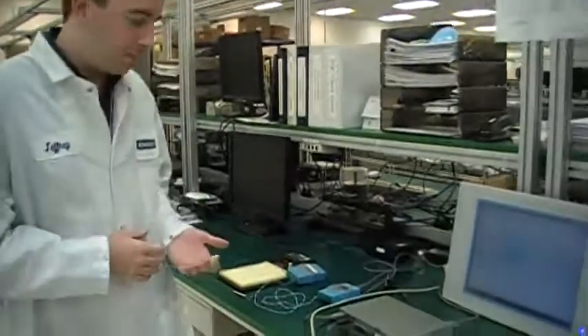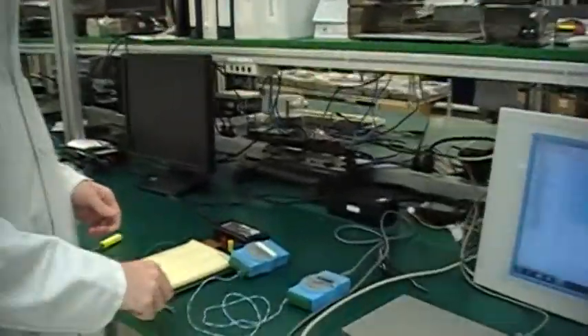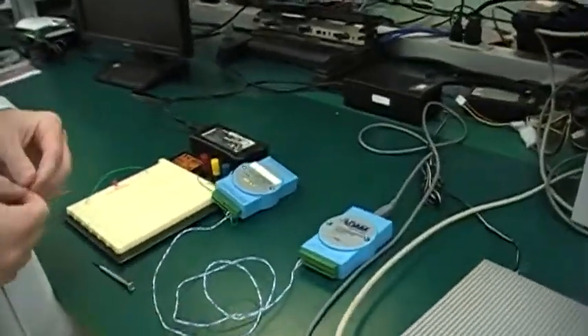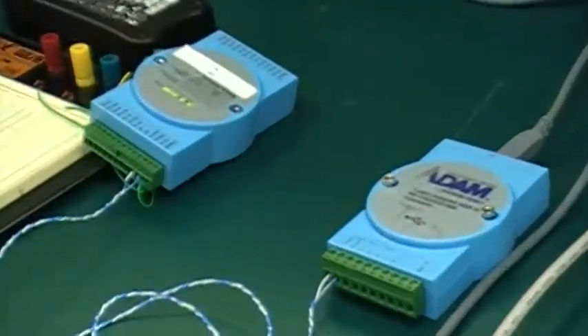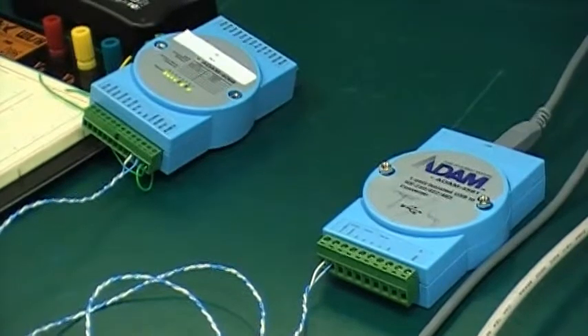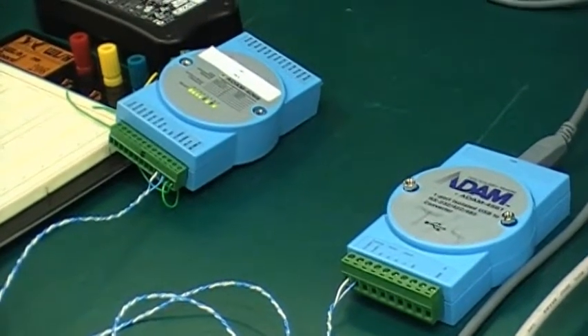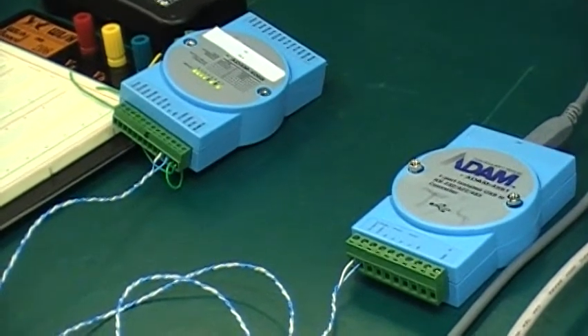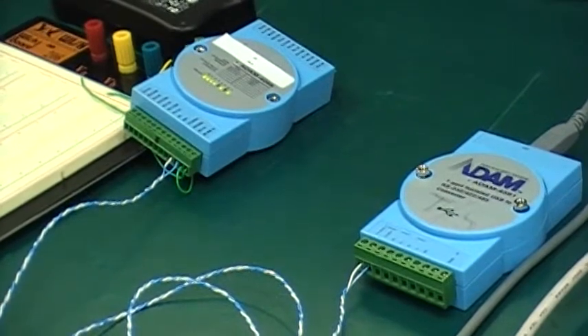Now the procedure is pretty simple. You'll need to connect one resistor across the plus and minus data signal for each end of the line. You can do this a lot of different ways, but for our video we'll connect directly to the terminating blocks of our modules.